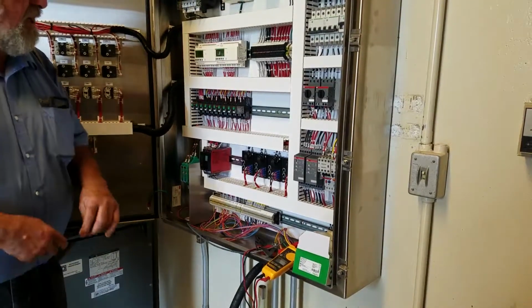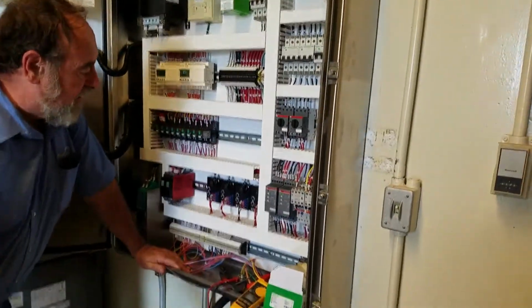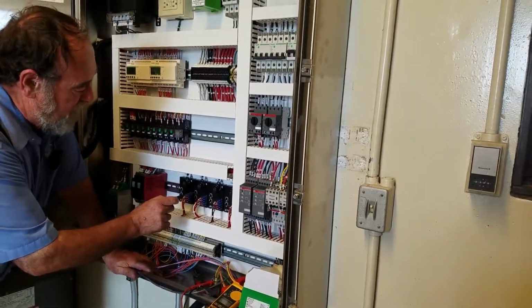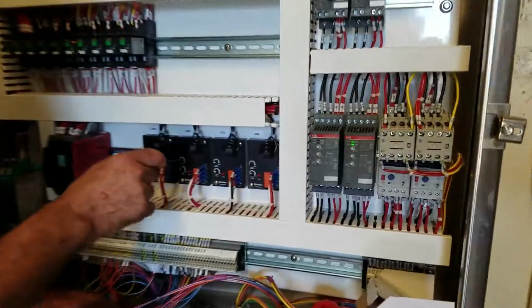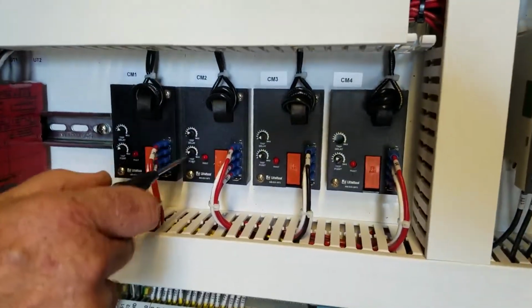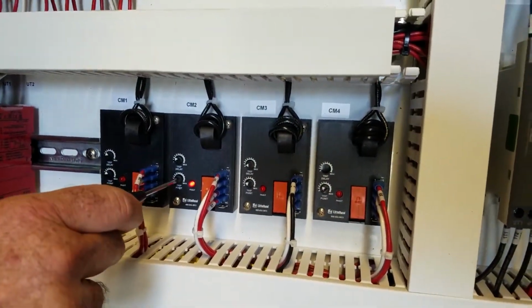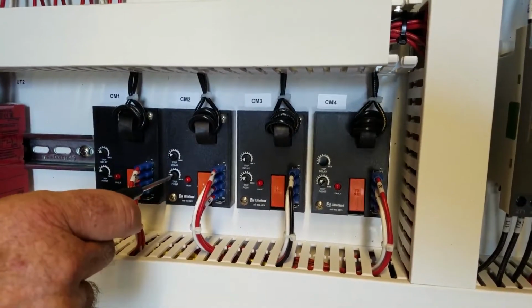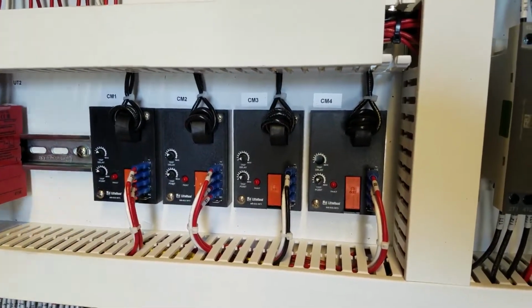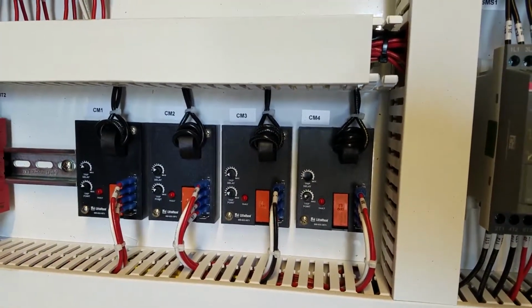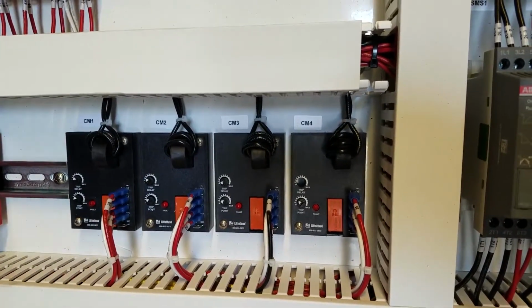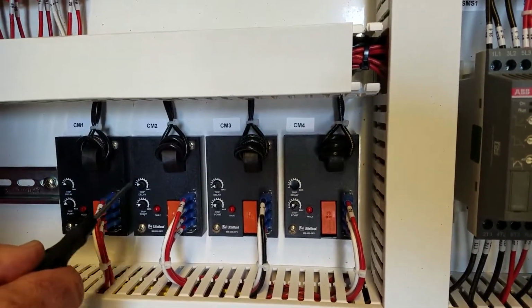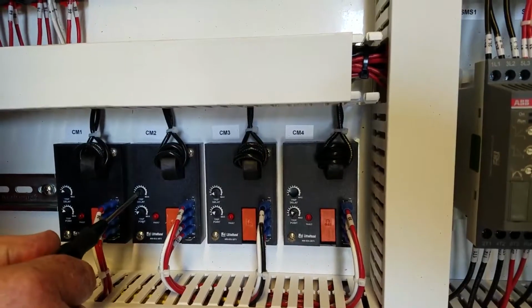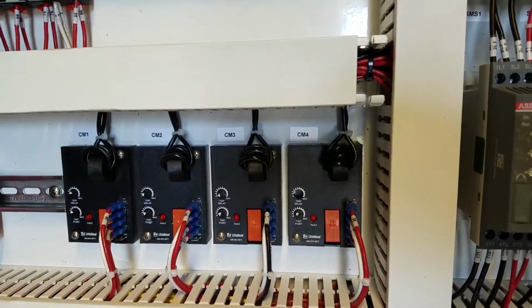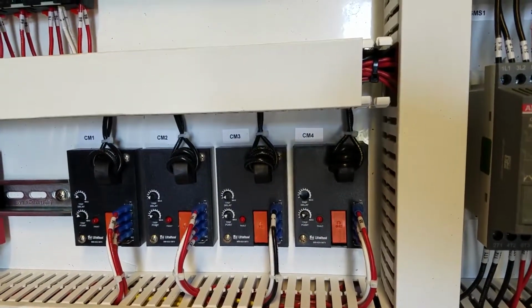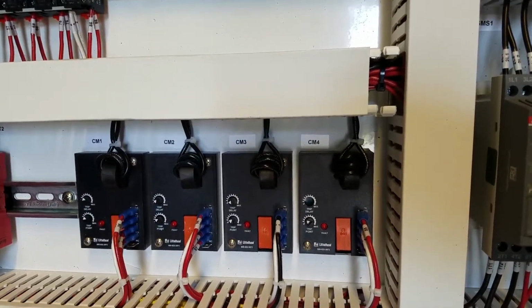These are your current monitors. The way you set a current monitor for the screen is you put it in the 10 o'clock position, you bring it down till the fault light just comes on, you bring it up about a notch. You bring it up a notch because you've got the oscillation of your current draw coming when it's going up and downhill, and you don't want any premature tripping. And then when you're done, put it back down to 9 o'clock, so if you get a mechanical jam, it's going to trip it out and do it.